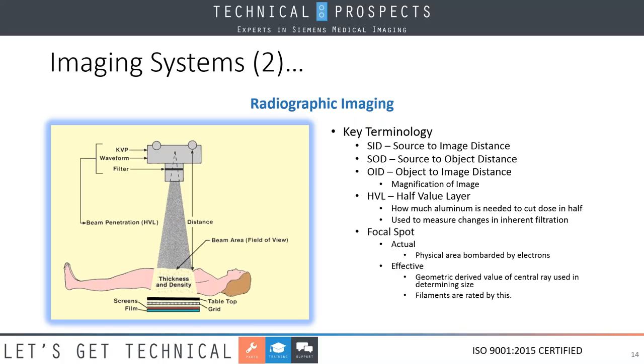Another term that's very important to us as field engineers is half value layer, because this is how we determine the age of the X-ray tube. Is it deteriorating over time? What's happening with the X-ray tube? Basically, what we do is we take aluminum and add it into the beam. When we can cut the output dose in half, this is called the half value layer. What this is showing us is the change in inherent filtration, inherent meaning built in, and this is showing us what's going on inside our tube, the amount of damage that's happening at the atomic level inside our tube, and the change in dose that's occurring.